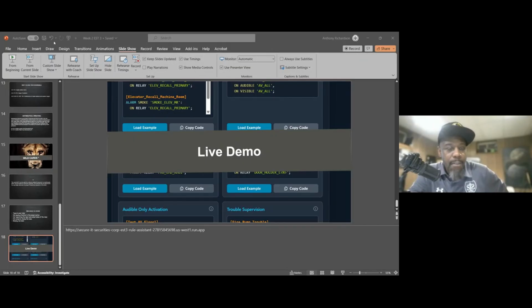So inside this object label, I just want to go through these tabs real quick. So we have AND groups. AND groups is a good place where you could use, let's say, a computer room. So you have smokes above the floor, you have smokes on the ceiling, you have smokes below the floor, and it's the raised floor that they have inside these computer rooms. So you would put devices inside of an AND group, so that way you would have this and that before an output activation.